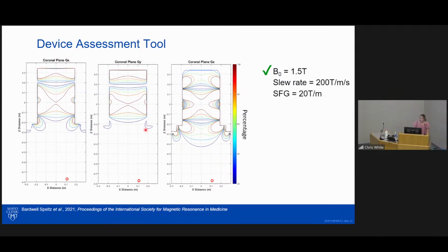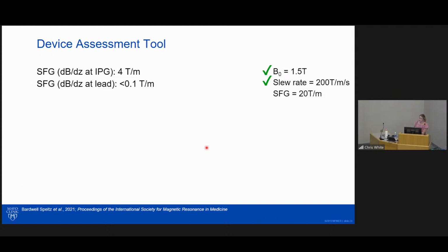And then this shows normalized contour plots as a percentage for the gradient slew rate calculated for the 3 gradient axes within the scanner dimensions. Here again, the red circle is showing the device IPG, and the blue circle is not visible because the Z coordinate was greater than 80 centimeters from isocenter. The lowest blue contour line is 120 Tesla per meter per second for slew rate. So based on these plots, we know that we can satisfy the slew rate condition. The program also outputs a value for DBDZ, or the spatial field gradient, which was 4 Tesla per meter for the IPG and less than 0.1 Tesla per meter for the lead. So we know that device condition can be satisfied.